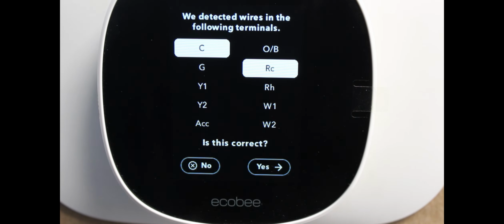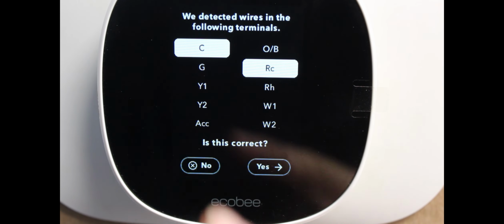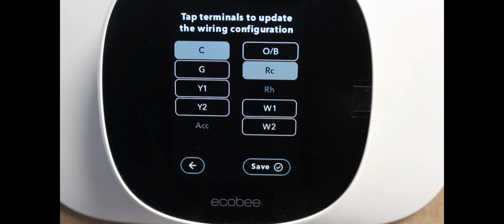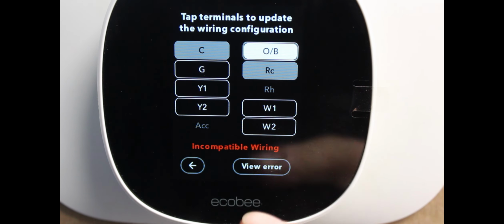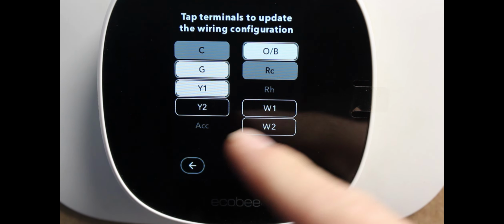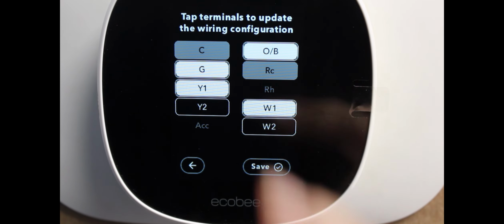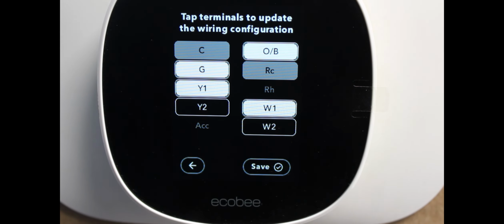Next thing it's going to do is tell you the wires that it detected connected on its subbase. In this case, I've only got it connected to a transformer, so I only have 24 volts in common. If you know you've got a wire connected but it's not showing on this screen, either it's not connected all the way or maybe it just didn't pick it up, and you can edit it. And this is where you can tell it what else is connected. In this case, we're going to tell it that it's got a heat pump with an electric backup heat source.